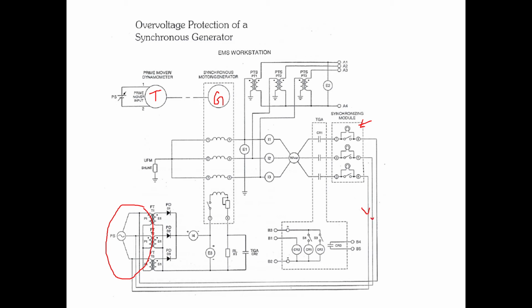So it is generating and producing the full load current, which means it is supplying to the grid. Now, I am not going to repeat the operation again. As you all know, first we have to make the turbine run close to the synchronous speed. Then we make this exciter produce voltage closer to 220. Then we slowly play with this supply and make sure the lamps are dim.